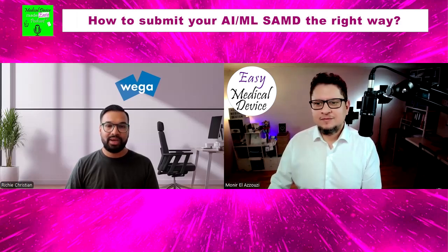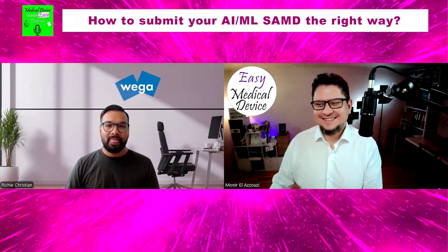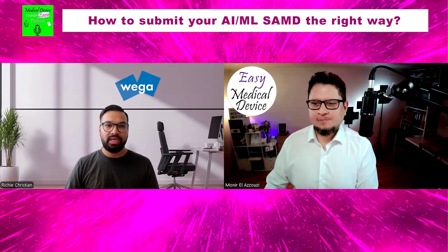Yeah. So one of the guidelines published by FDA around these good machine learning practices says that you need to select the best available reference. Now, obviously, that's a very subjective and broad term. So it's just such a cornerstone of your validation. So making sure that you have this right would be something, if you're targeting the US market, to actually go to the FDA and ask if your best available reference method is something they agree with, because a lot of time and resources are required to generate these reference data sets, and you want to make sure that you're doing it once and for all for your first submission. You want to make sure that it's really airtight in terms of your approach.